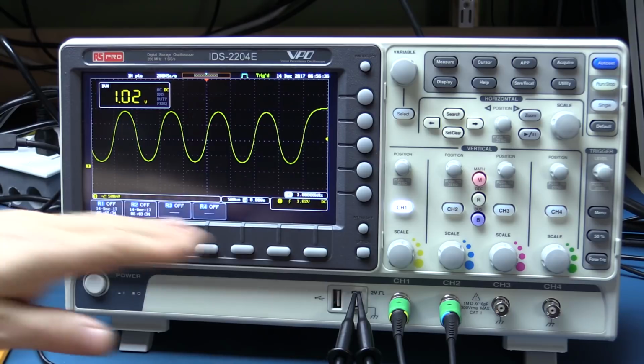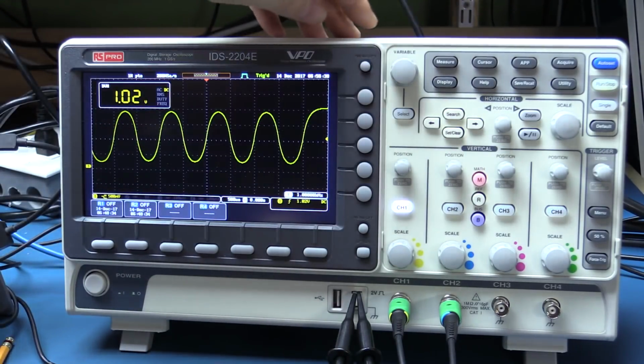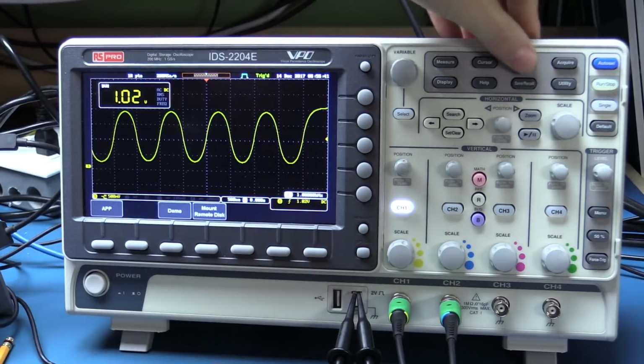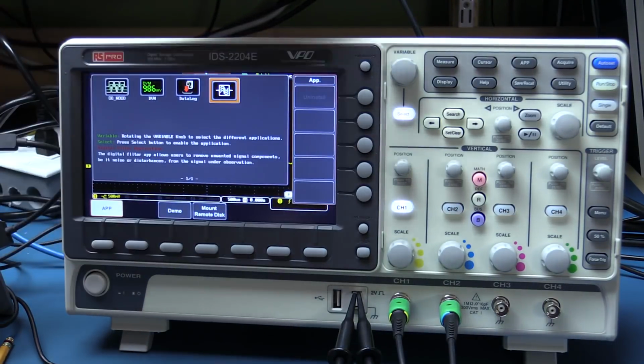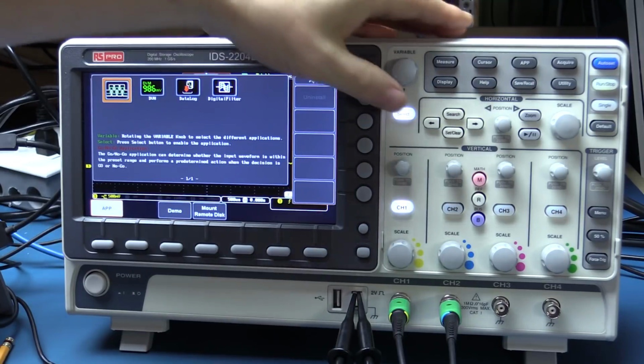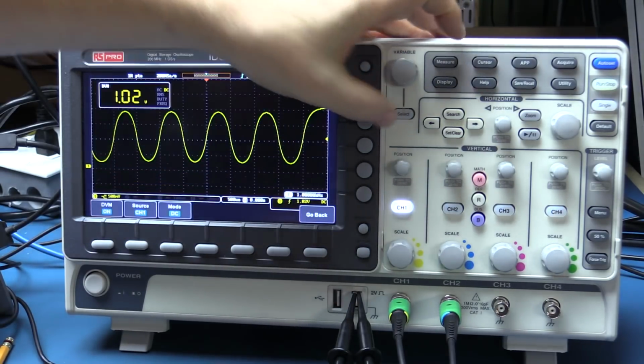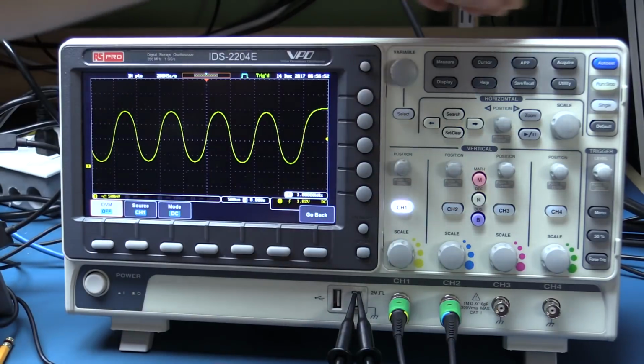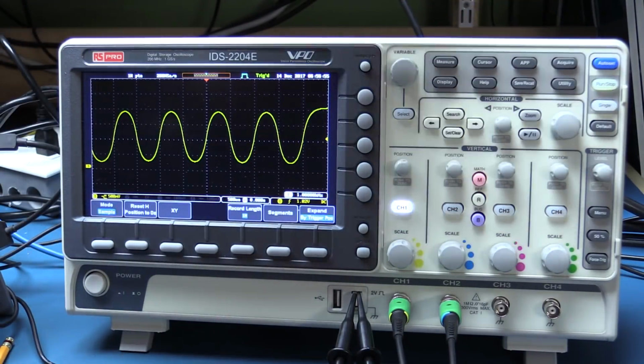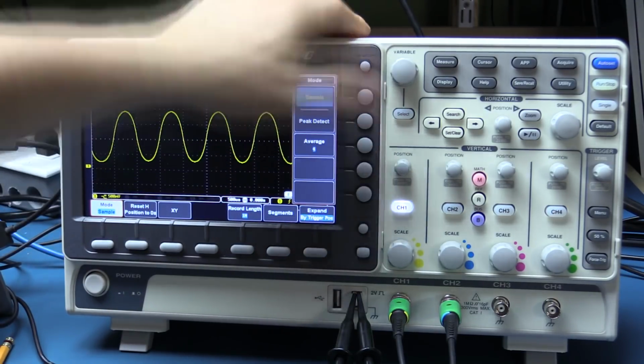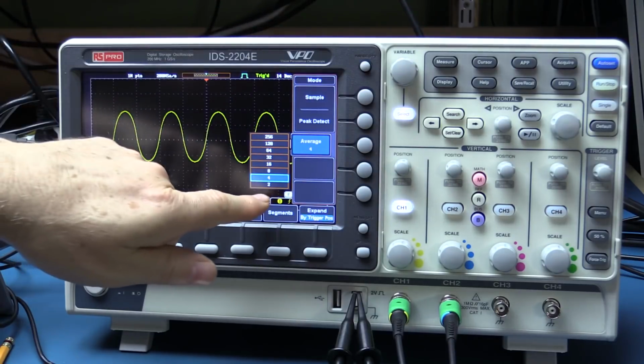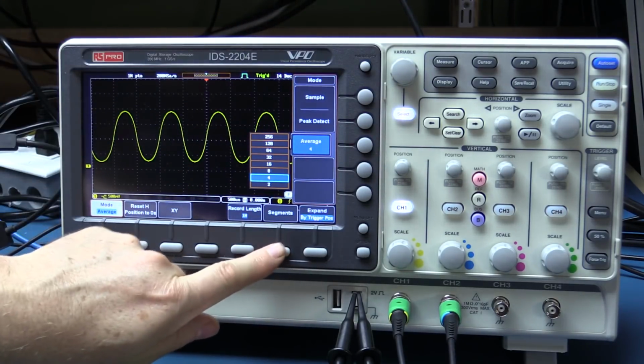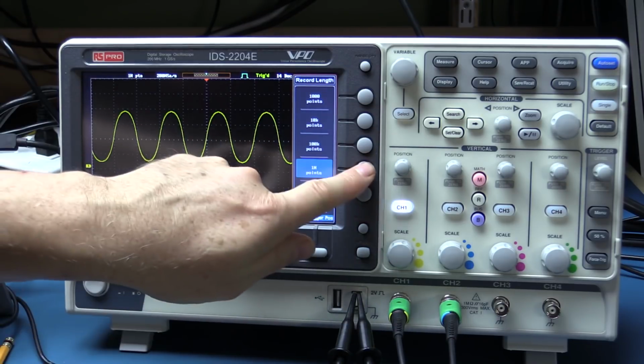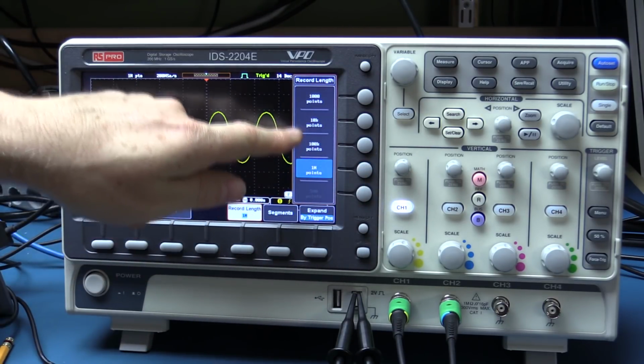It had saved those waveforms as reference waveforms. That's why I couldn't get rid of them. I just suddenly realized what it was from. Let's turn the DVM off just to clear it out of the way. Now if we go to acquire mode, what you can see here for acquire menus is sample, peak detect, average, and you can change the number of samples from 2 up to 256. You can change your record length: 1 megapoint, 100K, 10K, and 1K points for sampling.